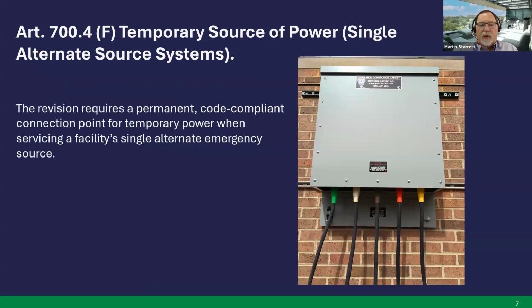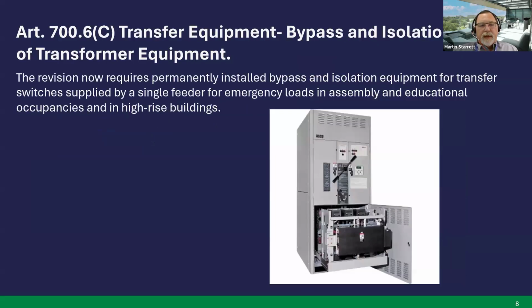In Article 700.4F, temporary source of power for a single alternate source systems, the revision requires a permanent code-compliant connection point for temporary power when servicing a facility's single alternate emergency source. Article 700.6C, transfer equipment, the bypass and isolation of transfer equipment. The revision now requires permanently installed bypass and isolation equipment for transfer switches that are supplied by a single feeder for emergency loads. This would be in assembly and educational occupancies and also in high-rise buildings.